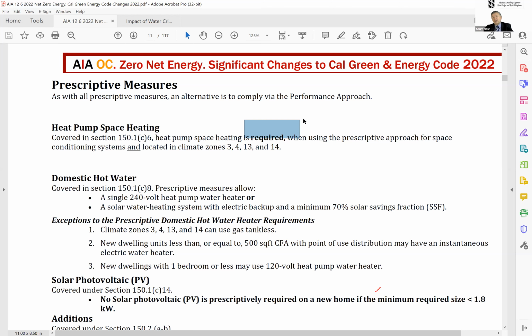The problem is if you go to mountain zones, where you're dealing with a giant delta T, let's say -10 to 75 for comfort, dealing with an 85 degree delta, your heat pump becomes enormously large. That's why you have hydronic systems there. You've got other elements and could still use the heat pump, you just design something different, like in Mammoth, where you can still use the heat pump for cooling.